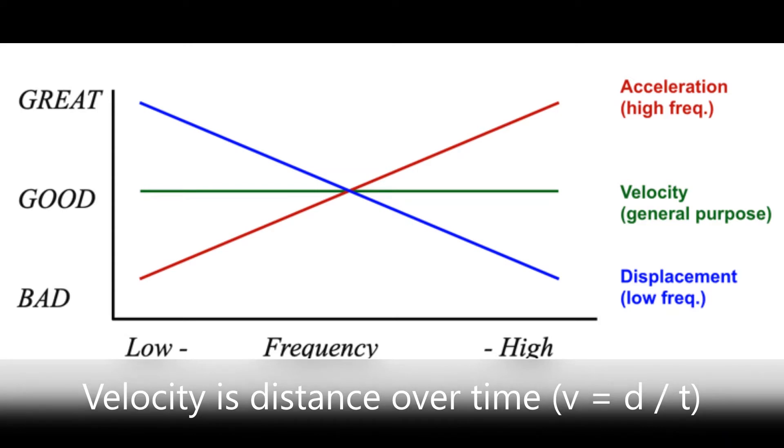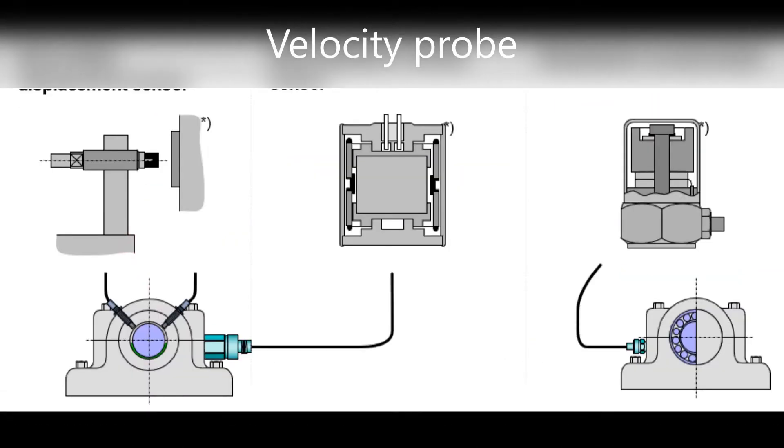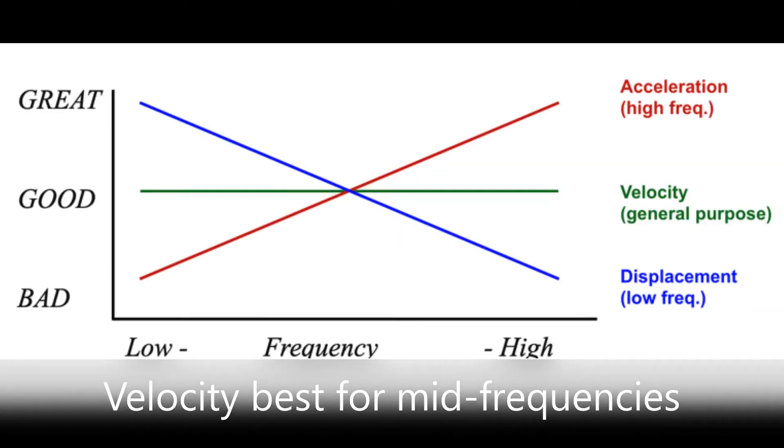Number two: velocity is the distance an object moves over a given time. In the past it was measured with a velocity probe, but the moving parts wear quickly and break. No longer is this common. Velocity is best for measuring the mid frequencies.